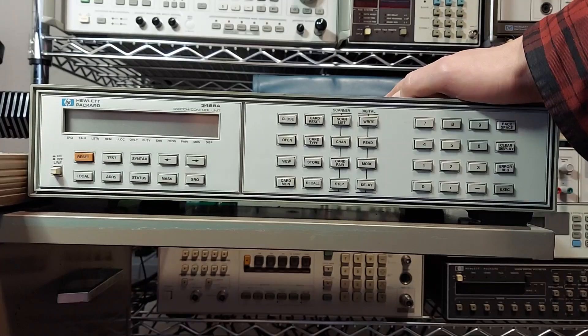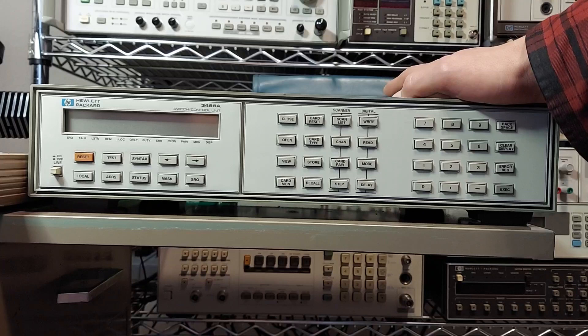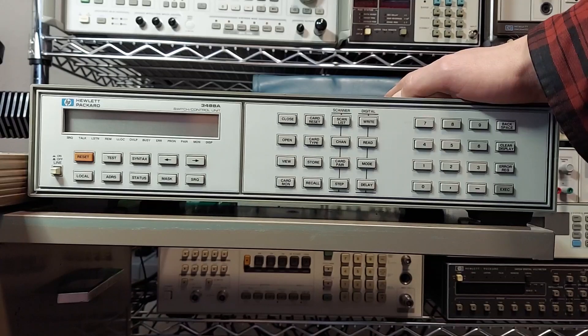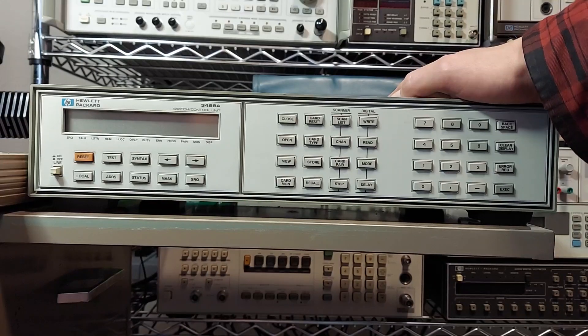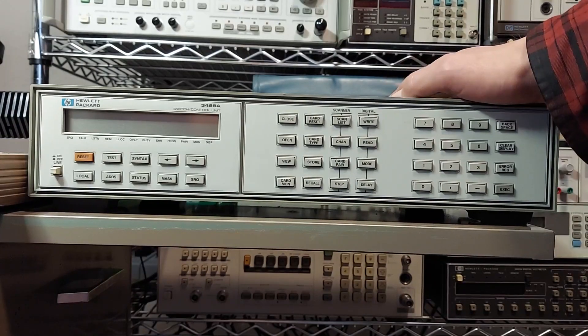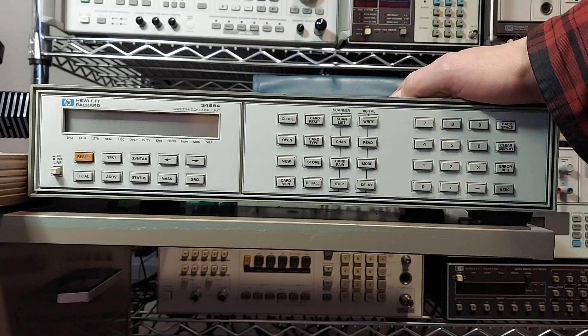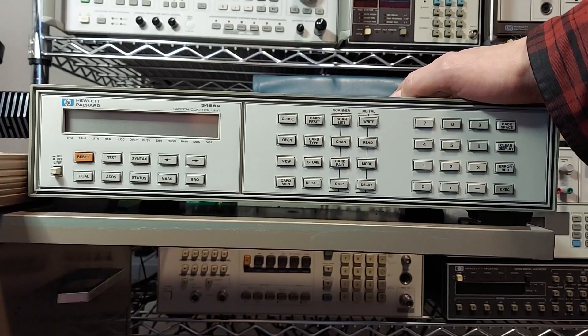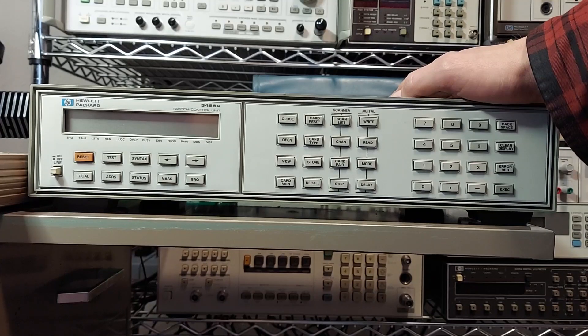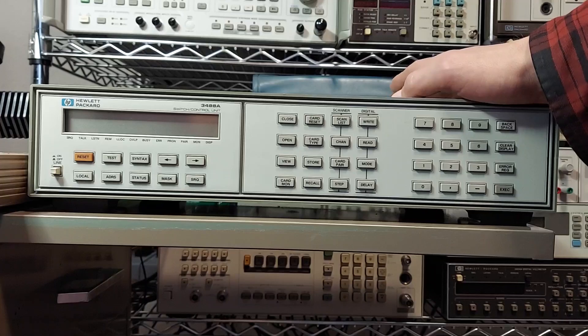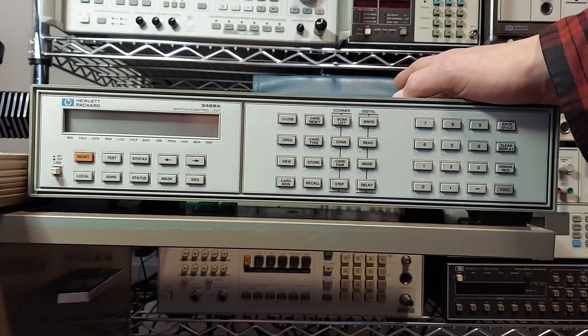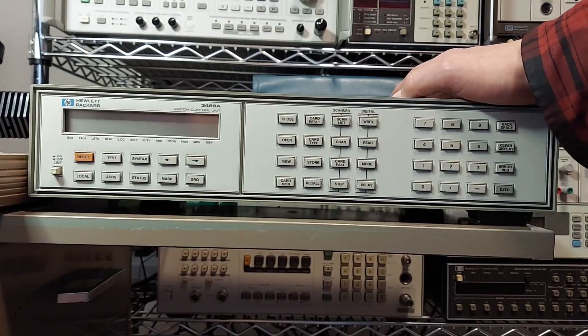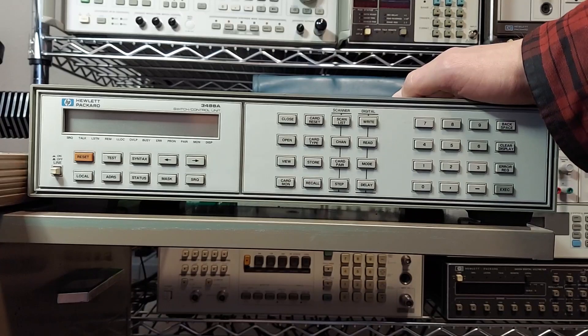One of the modules is a ten channel multiplex module. The other one's a general purpose relay module, it's ten channels. Another one is the VHF switch option which this one has. This has five dual port eight channel switches.